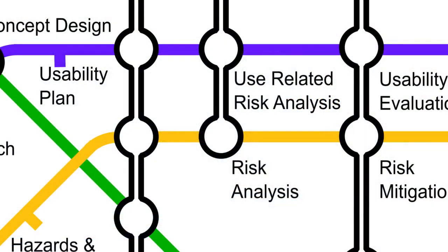Risk analysis has two parts. Firstly, identifying potential risks for the design, manufacture, assembly, distribution, use and disposal of the product. The second part is evaluating each of these against the hazards and harms I mentioned just now. You'll prioritize these risks based on their probability and the severity of the harm that could result. This allows you to focus on addressing the most important ones first.